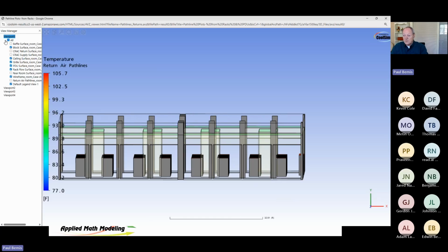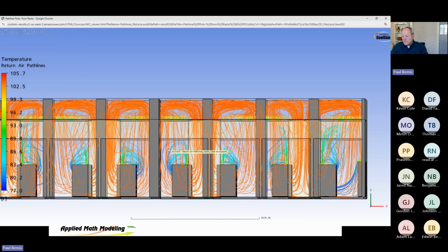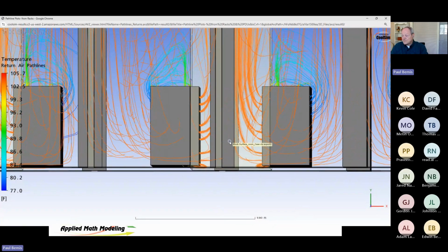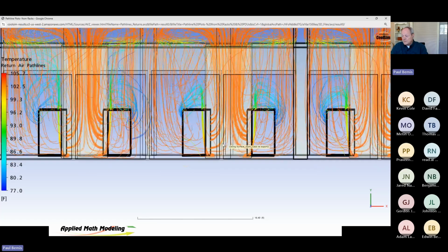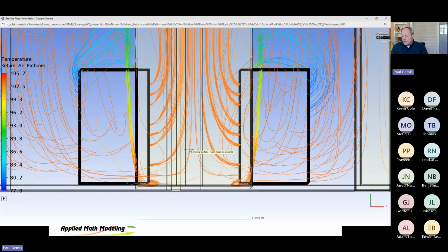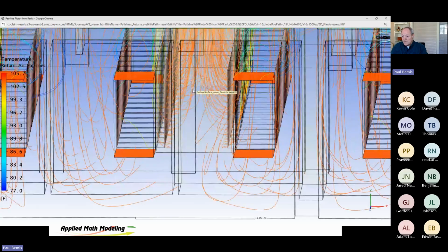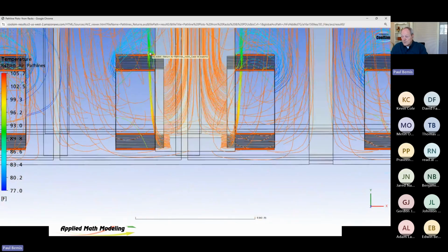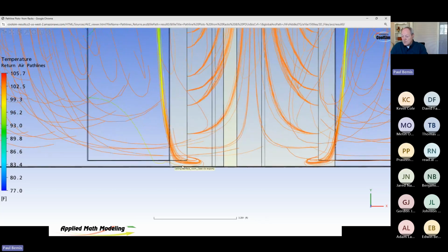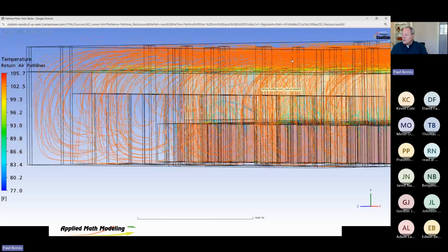So here, I'm getting into a little bit of the Ansys capability, but let me turn on those return path lines again. And what I wanted to show you is these airstreams banging into each other. So let me hide that. So there they are. So look at that. What I've got here is air coming out of each of these servers, and as it hits the center, it turns. They bang into one another. Pressure rises right there. Static pressure is higher in the center of that stream because the velocity went to zero or near zero. As the velocity declines, the pressure increases, and that causes it to go leaking back around those rack rails. And you can see some of them coming around the rack rail right there, coming into the cold aisle. It's coming underneath, which is not unusual. You do see leakage under the racks quite a bit. People forget to look down. Get down on your hands and knees and stare under that rack and make sure it's sealed up tightly.